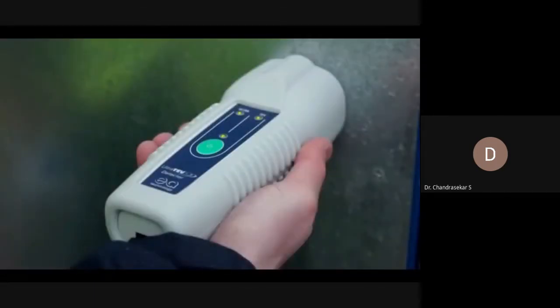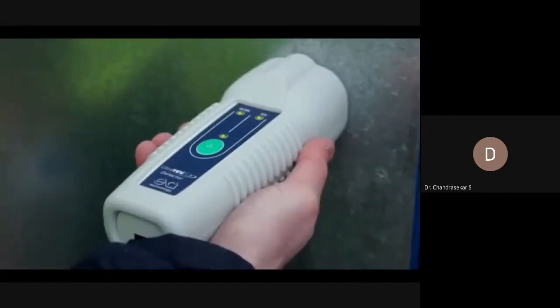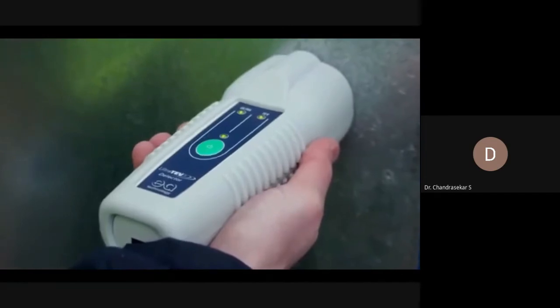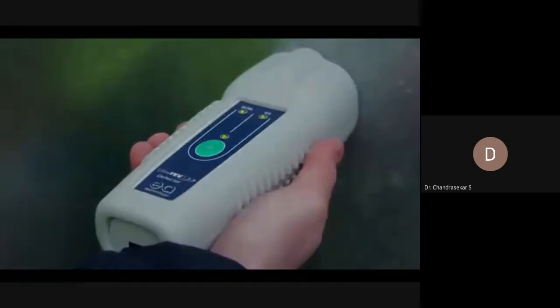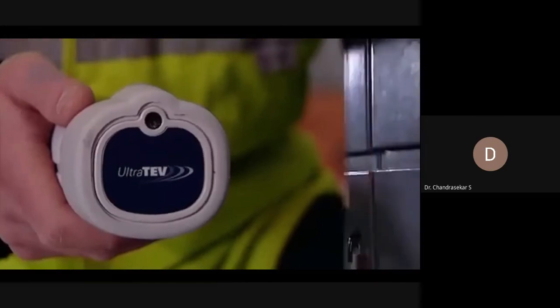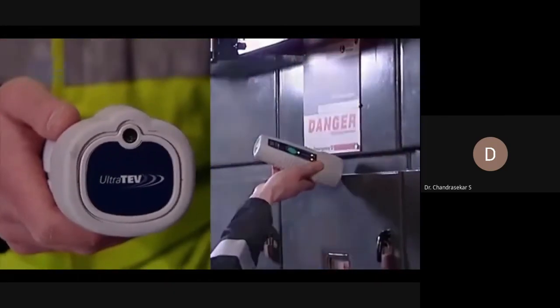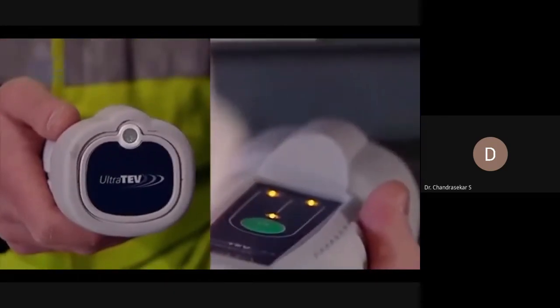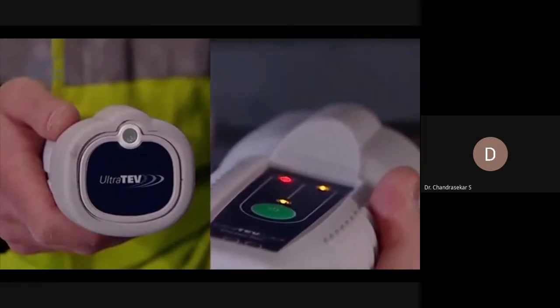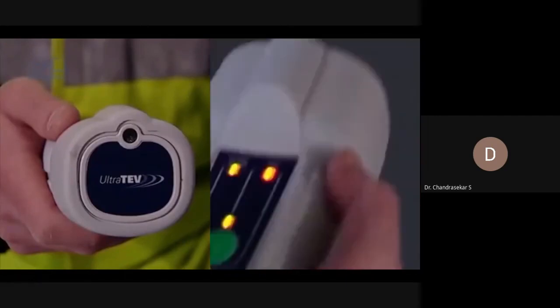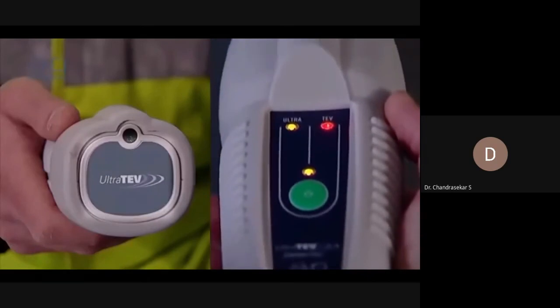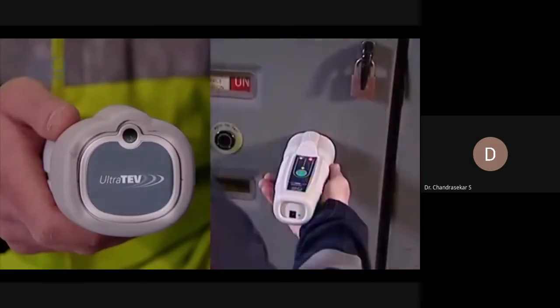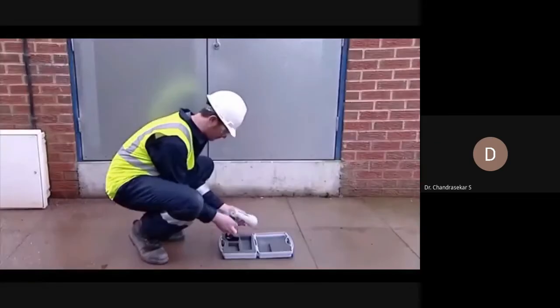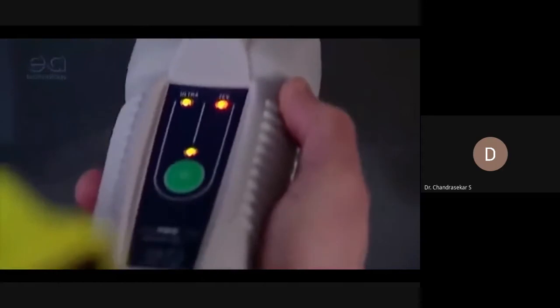Conduct a first-pass survey to assess if partial discharge activity needs further investigation with our award-winning UltraTev detector, featuring dual sensor technology with both ultrasonic and TEV sensor. It provides an immediate check for critical partial discharge activity. Easy to use with minimal training, it is the perfect instrument for detecting faults at an early stage.